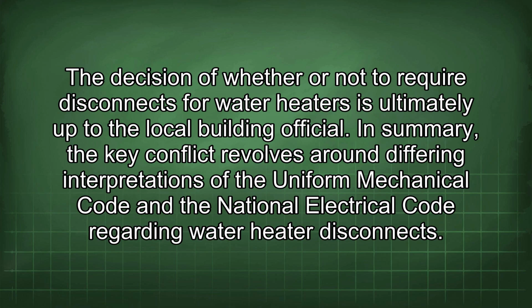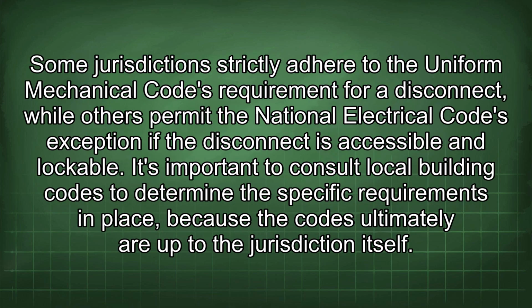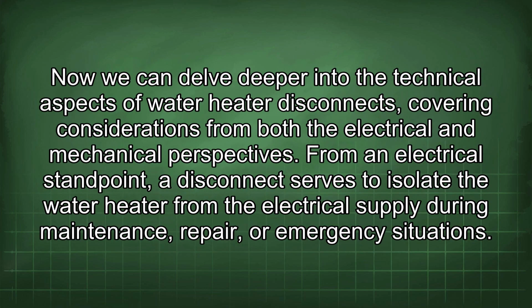The decision of whether or not to require disconnects for water heaters is ultimately up to the local building official. In summary, the key conflict revolves around differing interpretations of the Uniform Mechanical Code and the National Electrical Code regarding water heater disconnects. Some jurisdictions strictly adhere to the Uniform Mechanical Code requirement for a disconnect, while others permit the National Electrical Code's exception if the disconnect is accessible and lockable. It's important to consult local building codes to determine the specific requirements in place, because the codes ultimately are up to the jurisdiction itself. Now we can delve deeper into the technical aspects of water heater disconnects, covering considerations from both the electrical and mechanical perspectives.